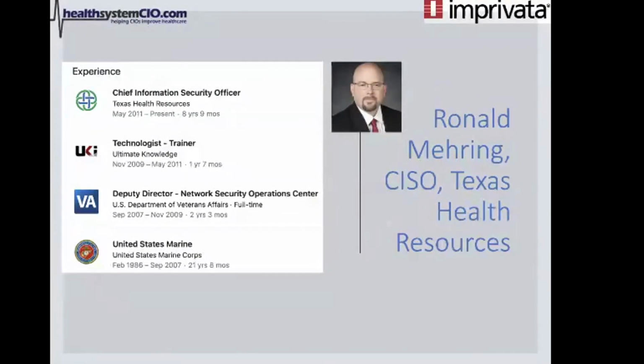Active Directory: when medical devices and a lot of their subsystems and ancillaries, let's say, are integrated into Active Directory, group policies that we traditionally put around traditional IT assets, you start putting those around medical devices in inappropriate ways. You find that you can break a lot of things at the worst time, by the way. It will always break at the worst time. They'll always break when somebody is in a surgery room and having surgery. And then all of a sudden things go awry. I don't know why that is, but maybe that's because they're being used at that time. But so, data flow control, GPO, Active Directory, those type of settings, we've seen that, and scanning.